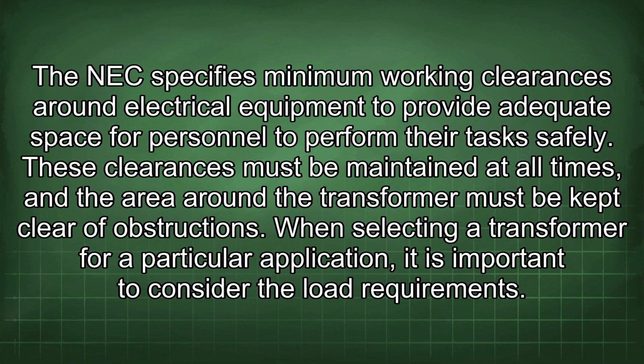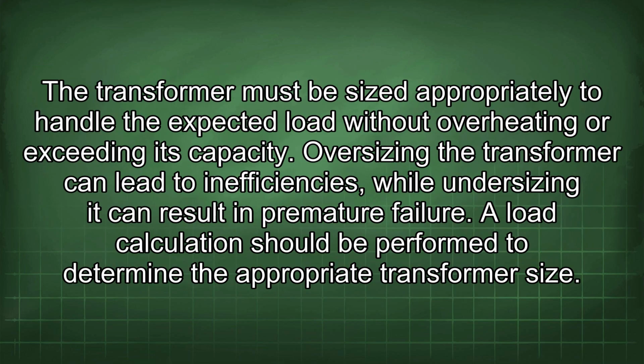When selecting a transformer for a particular application, it is important to consider the load requirements. The transformer must be sized appropriately to handle the expected load without overheating or exceeding its capacity. Oversizing the transformer can lead to inefficiencies, while undersizing it can result in premature failure. A load calculation should be performed to determine the appropriate transformer size.